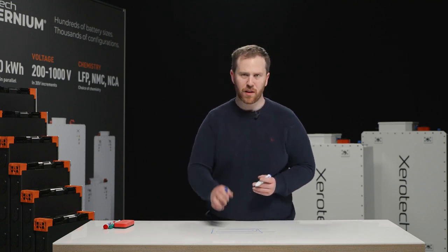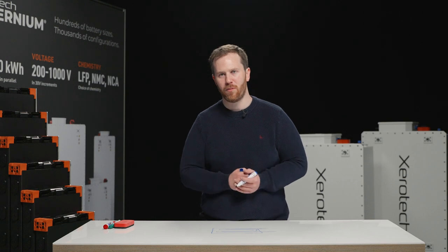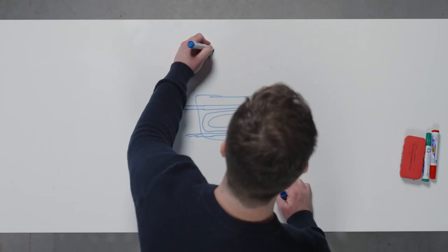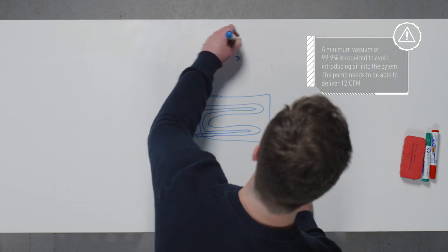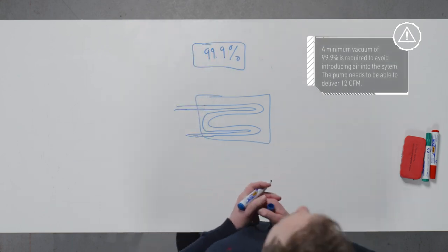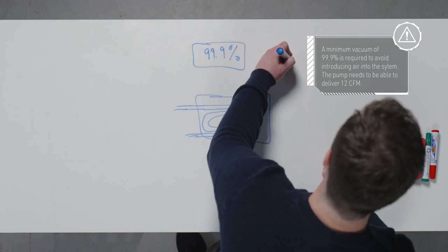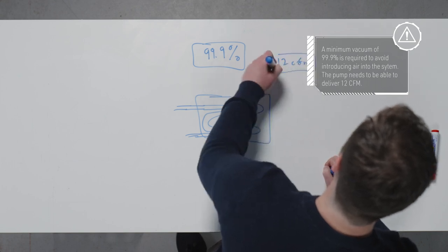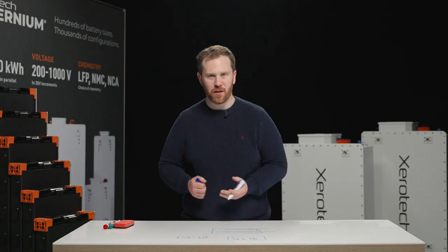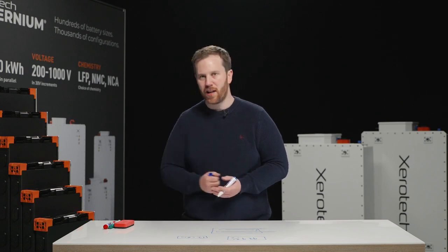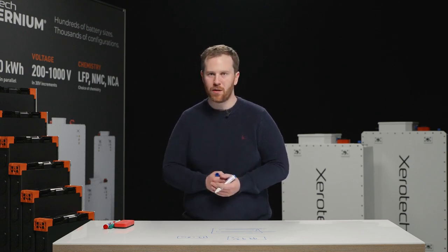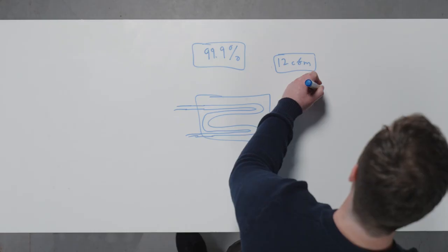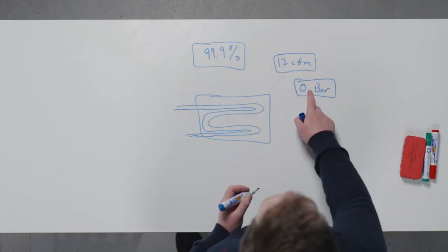For a Xerotech battery, it's really important that you pull a full vacuum on the system, a minimum of 99.9% vacuum using a proper vacuum pump. We'd recommend a pump of a minimum 12 CFM for doing this. So a standard Venturi type, airline type automotive vacuum system is not likely to be sufficient to do this type of vacuum pull down. You need to use a proper vacuum pump to pull a full vacuum down to as close to 0 bar as you possibly can in your real system.